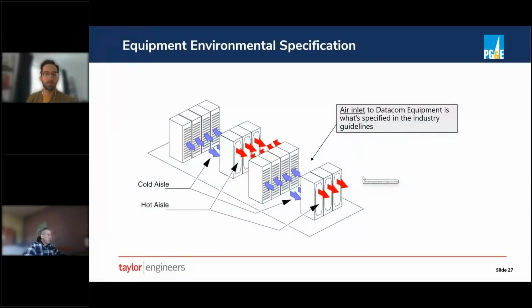So the first thing to talk about is where those environmental conditions are measured and monitored. And it's all about the inlet temperature to the computers. Don't particularly care about what's coming out of the computers. And as I said, data centers are typically racks and racks of computers. The computers, when they're air cooled, will pull air in from the front side of the pizza box, if you will, and blow it out the back.